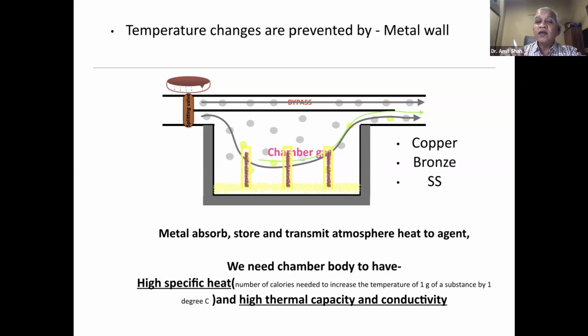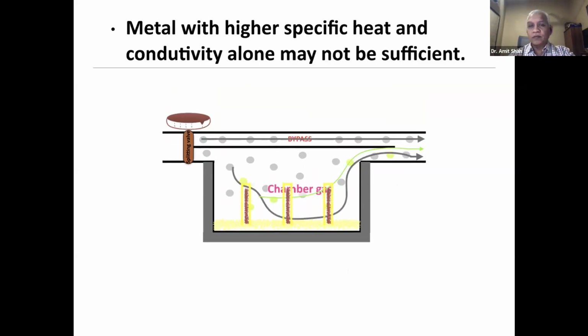And there are three main metals which are identified. The best one is actually copper. Copper, bronze, and SS, these are the three metals. And most of the modern vaporizers are made from copper because it has a high thermal conductivity and, what you call, a capacity to store and transmit into the liquid.